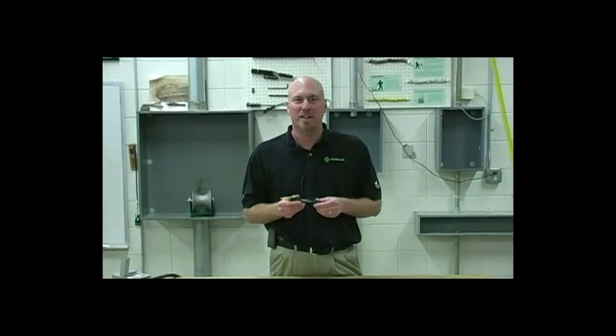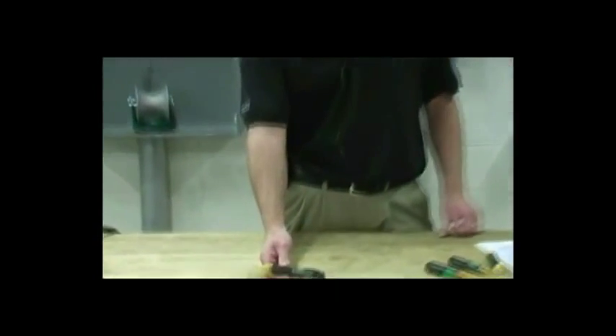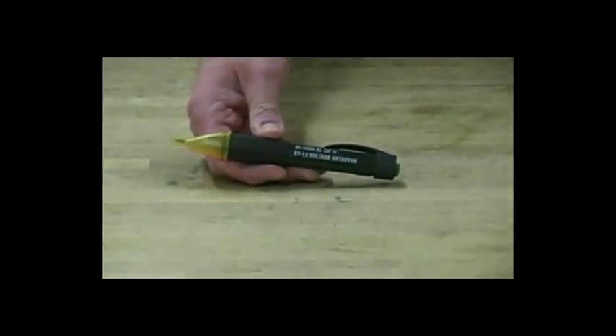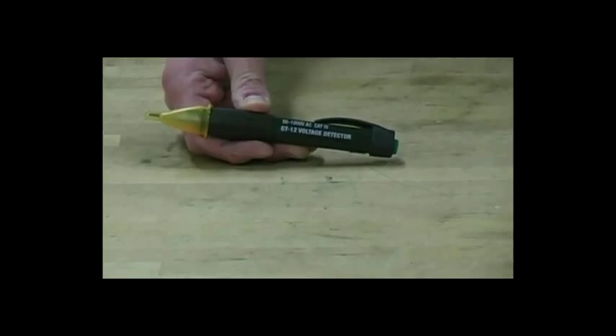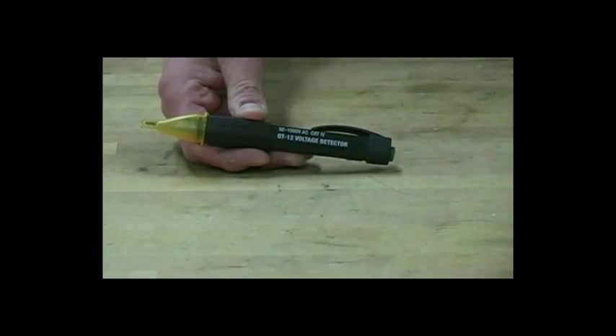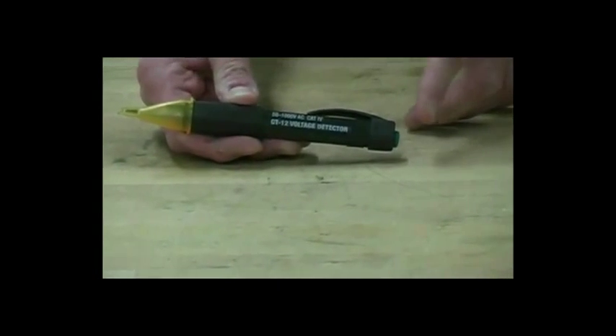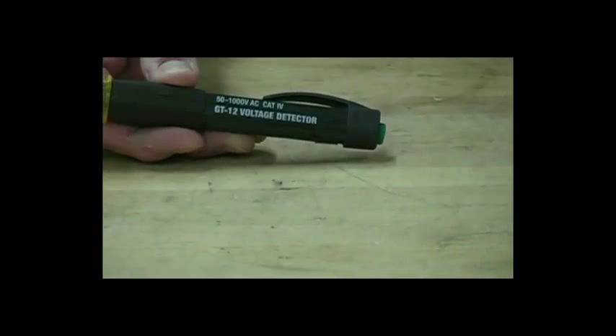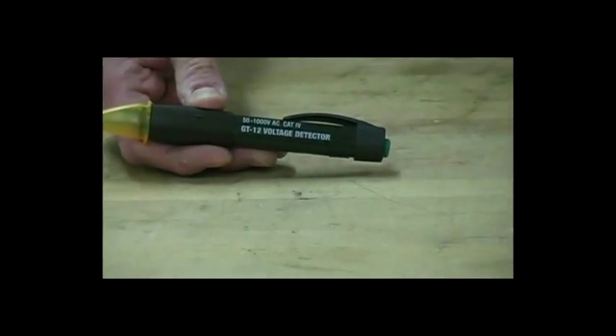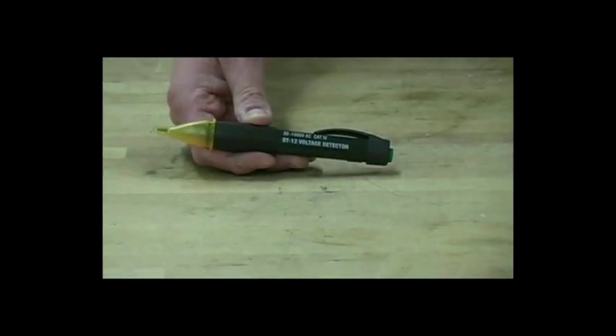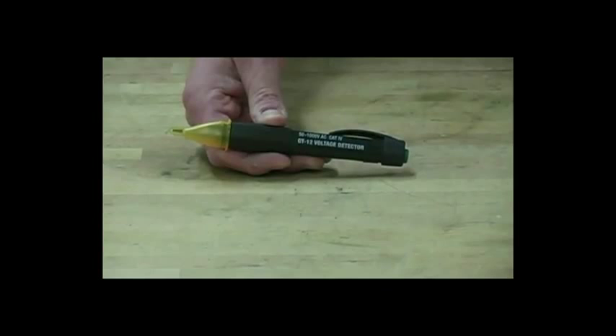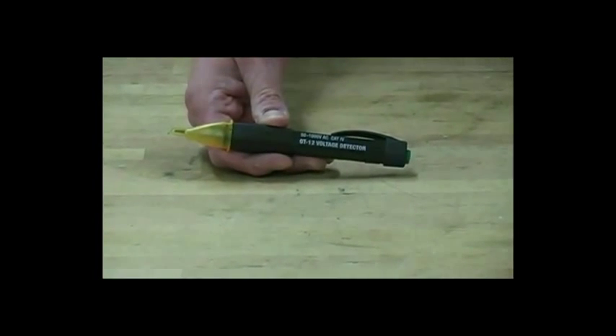The GT12 is a Category 4 1000 volt rated non-contact voltage detection tester. It is intended to check for the presence of AC voltage, signaling the user with an intermittent tone and flashing LED. The tone can be disabled using the smart on-off button. The GT12 has a self-test feature that continuously tests the integrity of the entire unit, including the antenna. The GT12 also features low battery indication and an auto power-off feature.